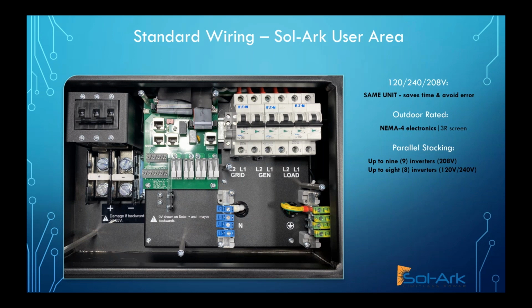From a voltage perspective, in terms of service voltages, we can do 220 volt single phase. We can do 120/240 volt split phase, the predominant residential voltage, and we can do 120/208 volt 3 phase. And we'll talk about that more in a minute. The 120/208 volt 3 phase really opens up some commercial possibilities for us. But the important thing to note is there are not different SKU numbers for this. If you have a 12K inverter, you can do 50 hertz grid, 60 hertz grid, 220 single, 120/240 split, or 208 volt 3 phase. It's the same inverter, right? We don't have a bunch of SKUs. You don't have to figure out which frequency it is, none of that stuff. These are settings in the inverters.